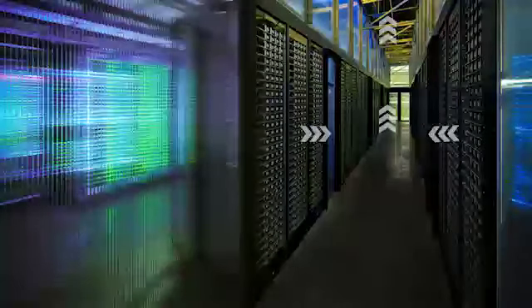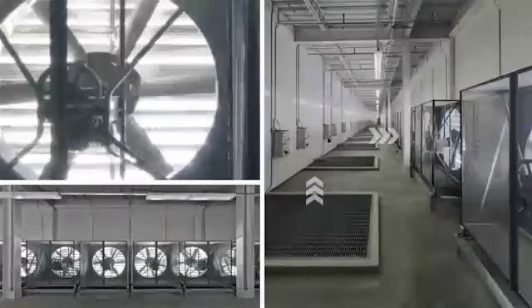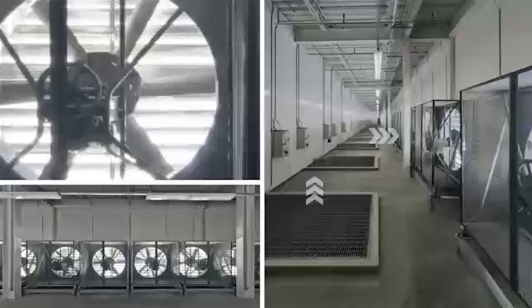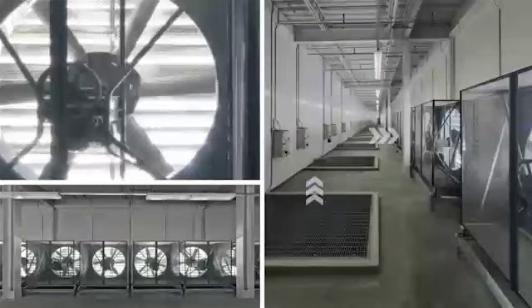We're inside a hot aisle containment section, and the air is coming in, and we just exhaust that up into the ceiling plenum. That hot air then is directed into an exhaust section with exhaust fans that blow the exhaust heat out. One of the things that we mentioned earlier was the exhaust plenum that we incorporated in Forest City as well as in Luleå. The idea there is that if any precipitation were to backflow through that section, we have a contained space. All our openings down into the data hall are curbed to control any water that might make its way onto the floor.